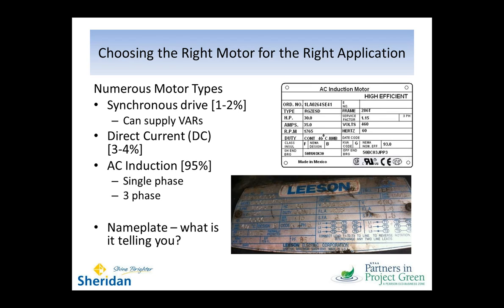The disadvantage of the induction motor is that it's going to consume reactive power, creating its magnetic fields, and it's going to create what we call a lagging power factor. The rotor will also typically spin a few percentage RPM below the rotating electric field, because it's essentially being dragged by that rotating field. So it has a torque characteristic that will see it hold its speed within a few RPM until it reaches a breakdown torque, a breakdown threshold, at which point it'll basically go to stall, and it'll create a condition we call locked rotor.